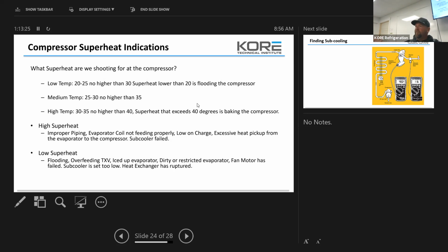If you guys run into an overheating situation, I'd say by raise of hands, but half of you are online. How many times have we gone out and taken an overheating situation out of play, and then two days later we're changing the compressor, right? So if we have an overheating situation, we need to note on our service ticket: may have caused damage to compressor. Because it does almost every time.